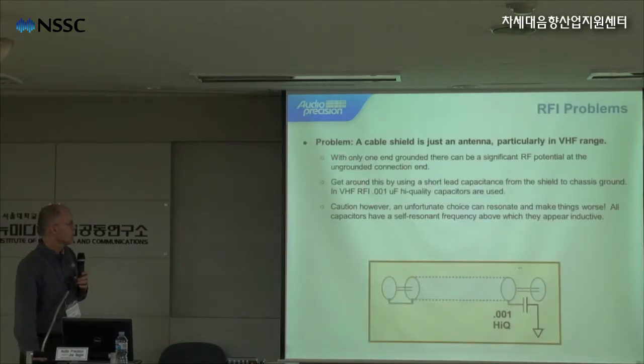So some of the tips. Radio frequency interference problem. A cable shield is just an antenna, particularly in the VHF range of the radio spectrum. With only one end grounded, there can be a significant RF potential at the ungrounded connection end. So one way to get around this is to use a very short lead capacitor from the shield to chassis ground. In the case of VHF radio frequencies, a 0.001 microfarad high quality capacitor connected between the shield and ground can be used. You should be careful, however, an unfortunate choice can cause resonance and make things worse. All capacitors have a self-resonant frequency above which they appear inductive.